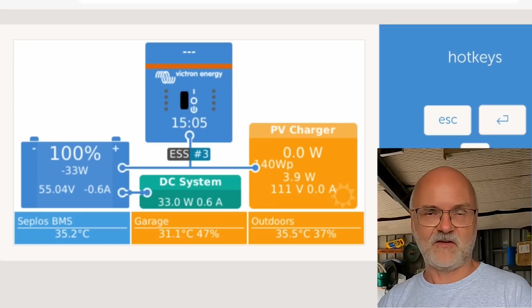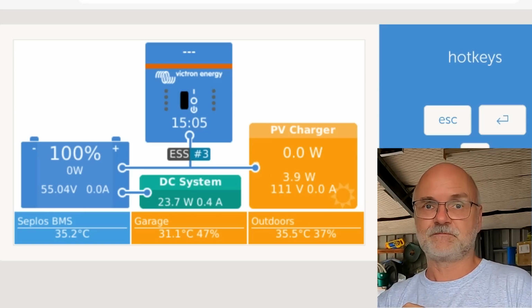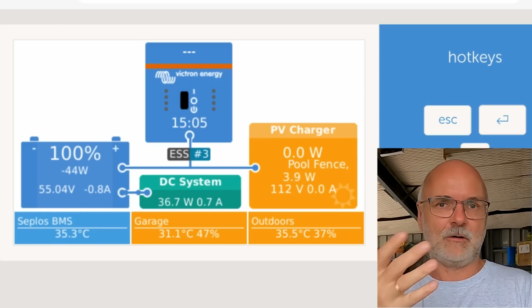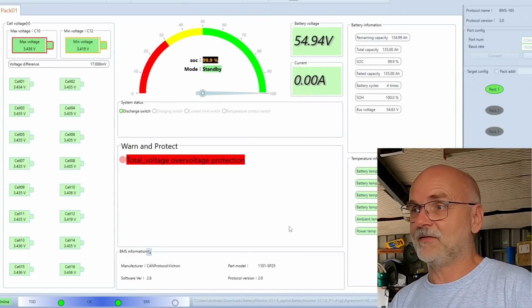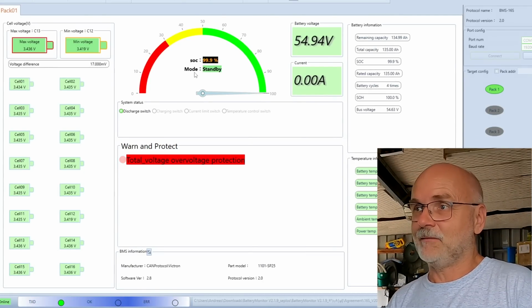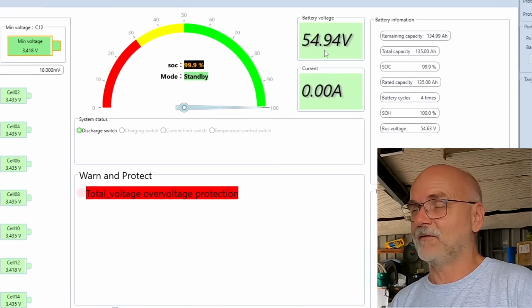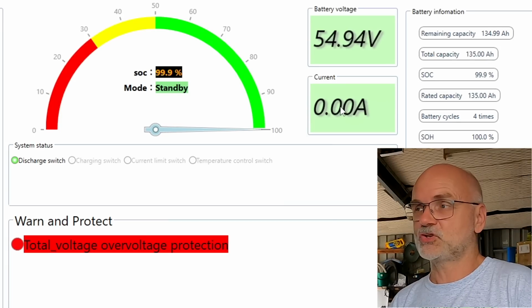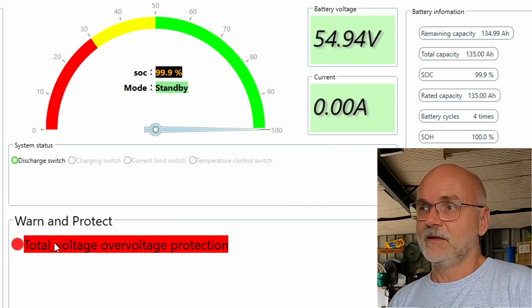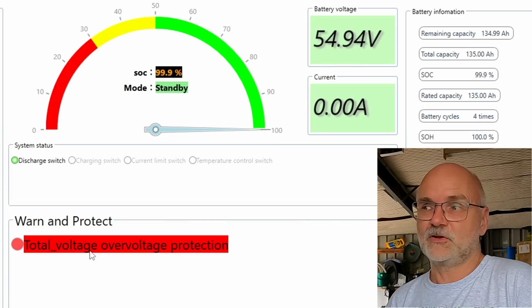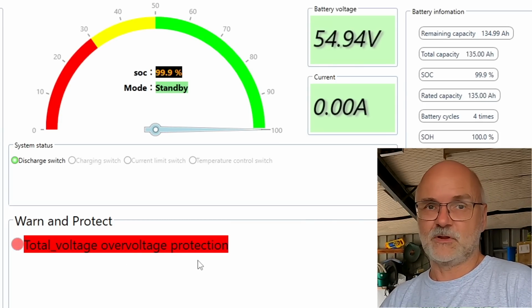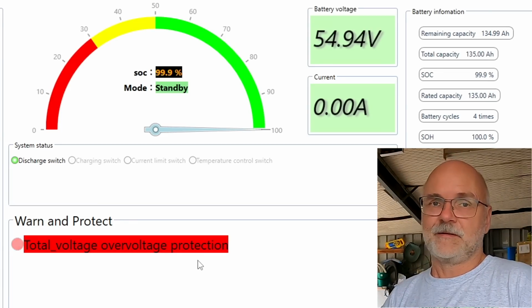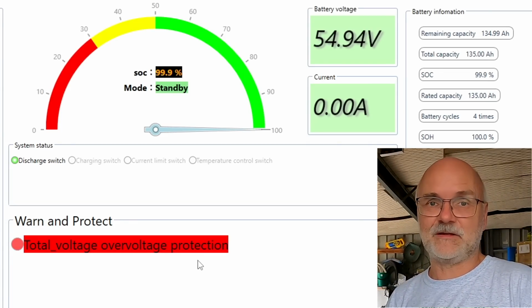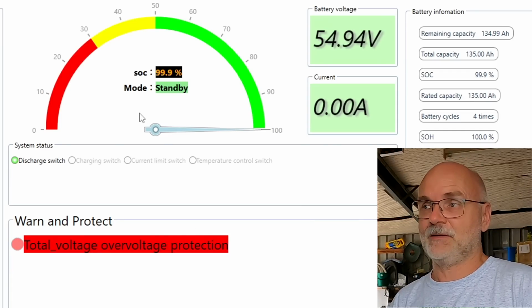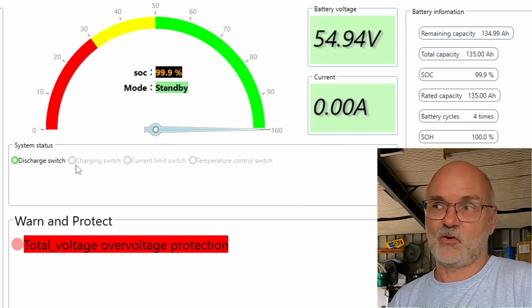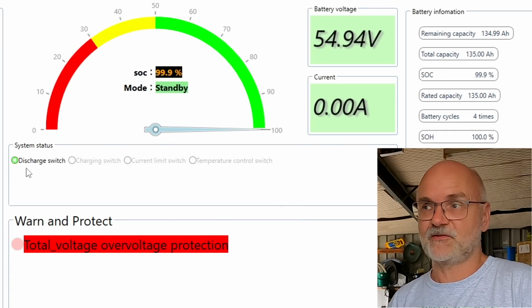So 55.2, this is the maximum charge, and then 55 allows charging again. We are now having a look at the slave BMS, and we can see it is at 54.9 or 55 volts. There's no charging, no current going in or out. We have a total voltage over voltage protection because we have reached 55.2 volts, and the BMS stops or disallows further charging. Charging switch is turned off, but the discharge switch is still on.